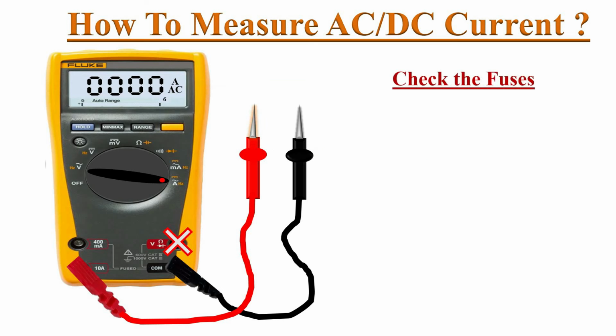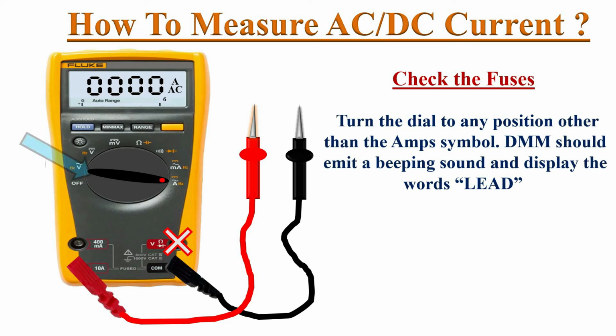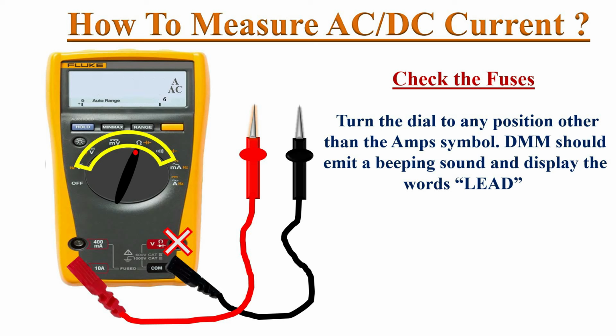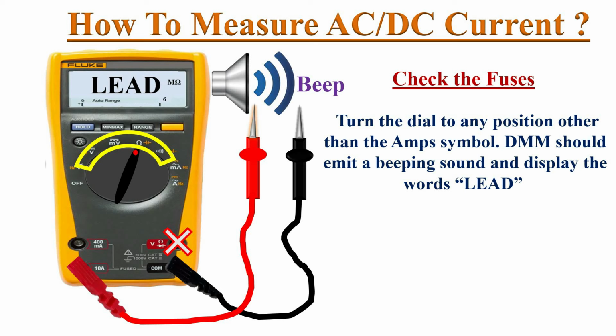First, we must check the correctness of the fuses inside DMM. To do this, turn the dial to any position other than the amps and milliamp symbol. DMM should display the word "lead" and must emit a beeping sound. If this happens, then we can confirm that fuses inside the DMM are okay. Otherwise, fuses are blown out. We cannot take measurement without replacing fuses.